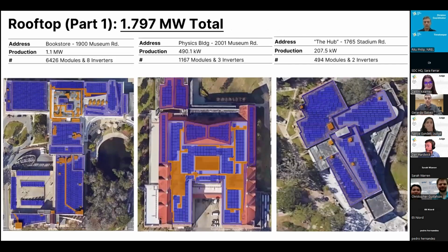So on the left here we have our sites. We have 9 sites in total, 11 buildings and 2 carports and 2 historical buildings. Our roof orientation is landscape east to west facing modules. They are near flush with a 10-degree tilt, ideal for Florida conditions, with 4-foot pathways and 4-foot setbacks from all edges and roof obstructions that are compliant with the NEC.